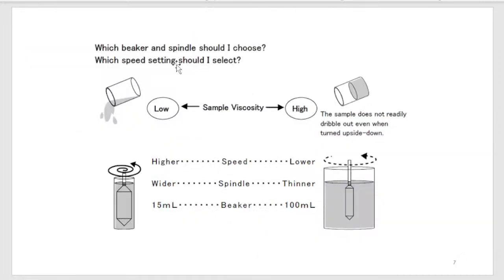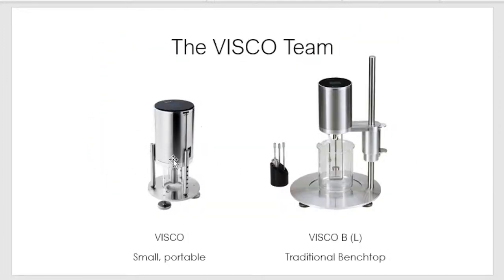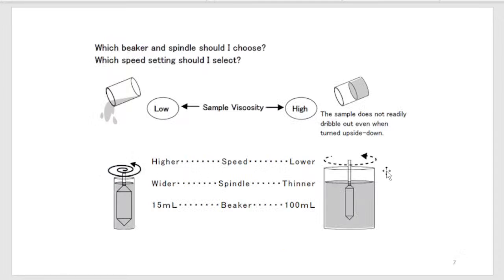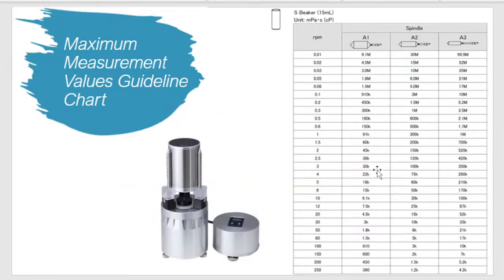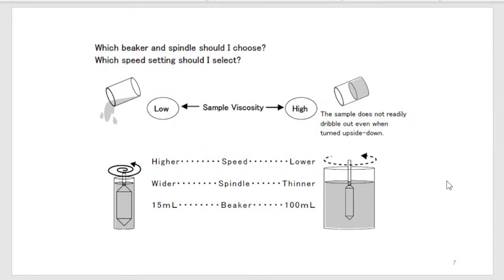This distinction is applicable to the portable VISCO because the VISCO BL is standard — it uses a 500 mL container, so there are no different container options. The VISCO does have two different container options. If you're using the temperature controller with the VISCO, you'll be using the small beaker only, which holds 15 mL.